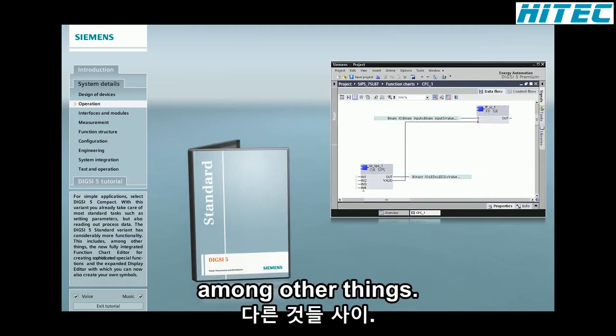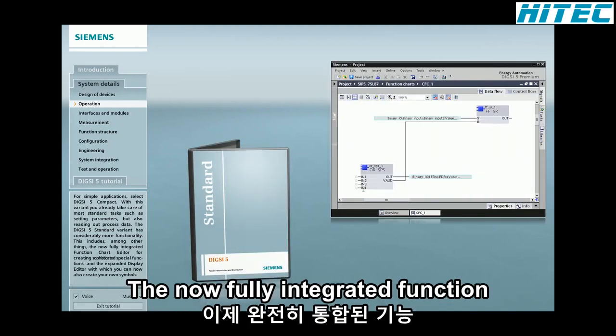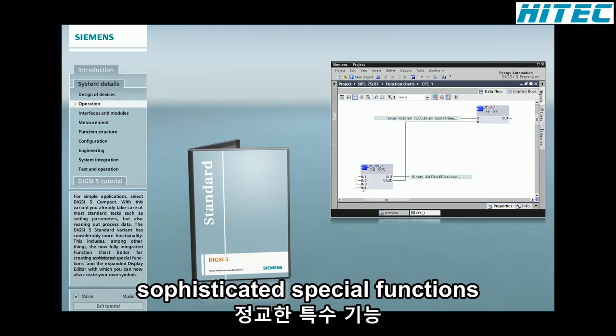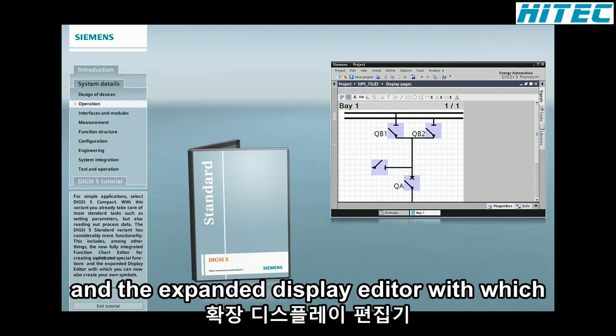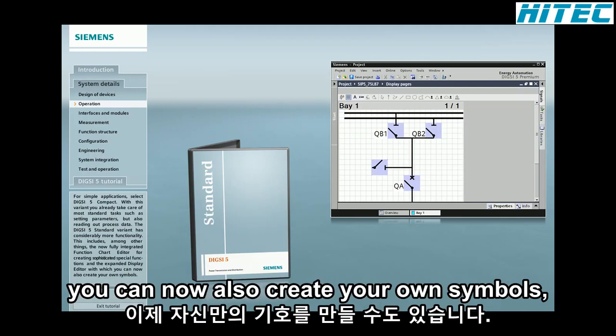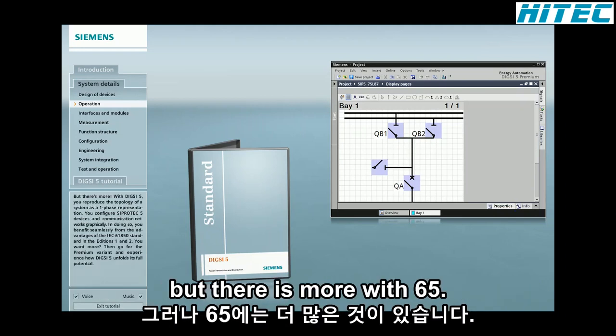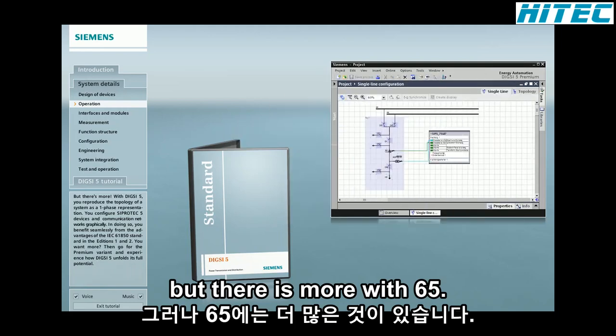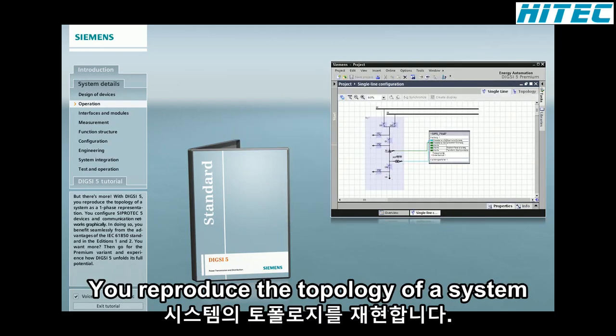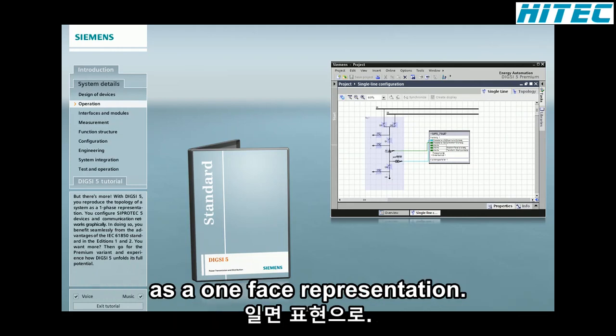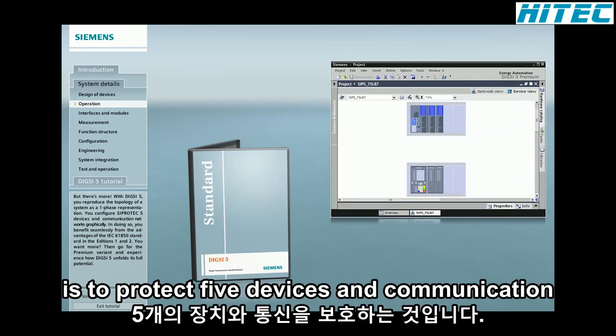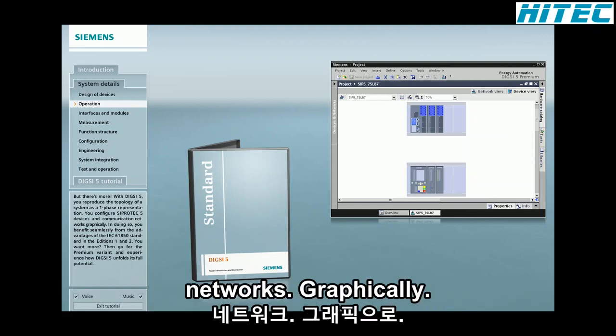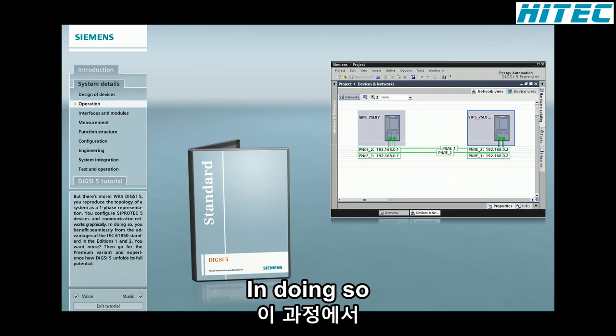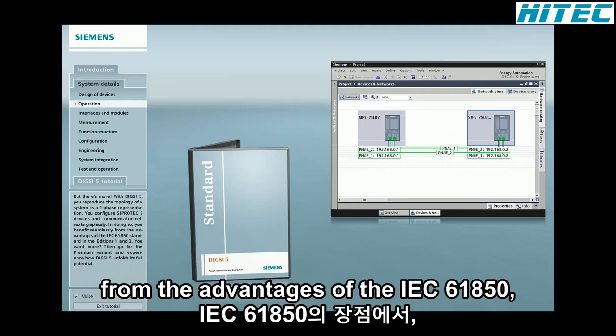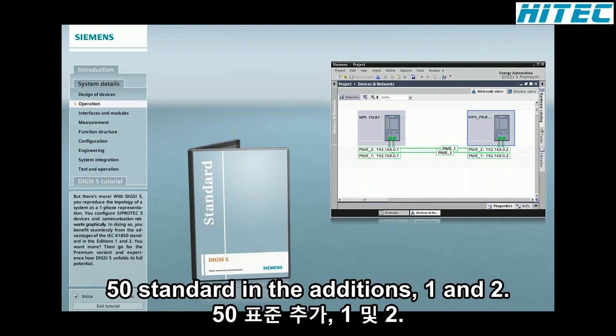This includes, among other things, the now fully integrated function chart editor for creating sophisticated special functions, and the expanded display editor with which you can now also create your own symbols. But there is more. With DIGSI 5, you reproduce the topology of a system as a one-phase representation. You configure SIPROTEC 5 devices and communication networks graphically. In doing so, you benefit seamlessly from the advantages of the IEC 61850 standard in the editions 1 and 2.